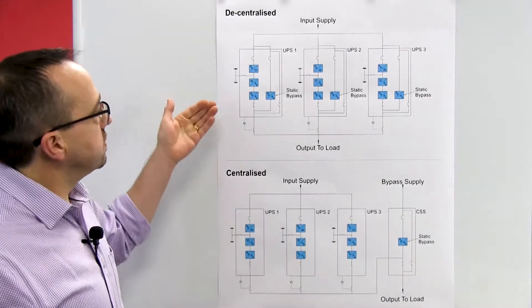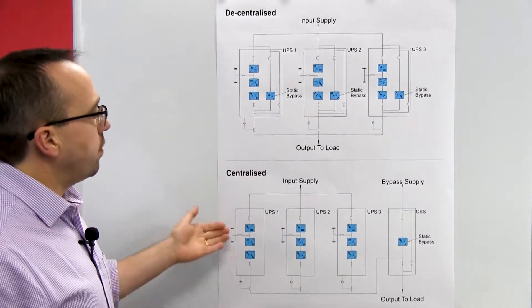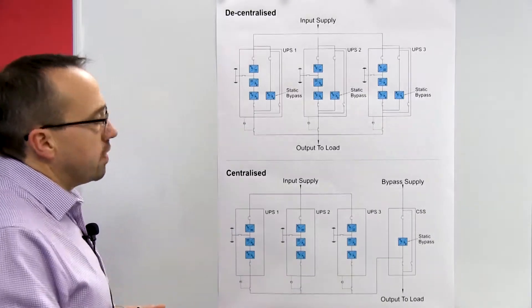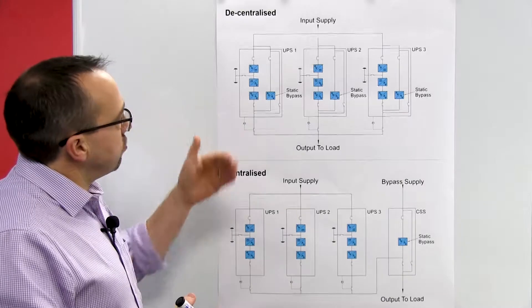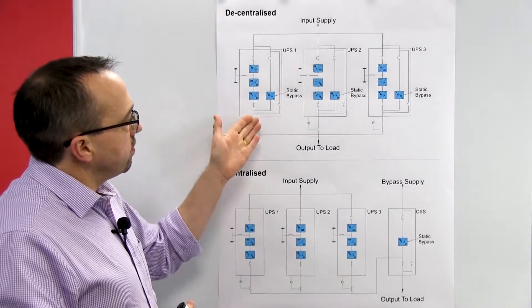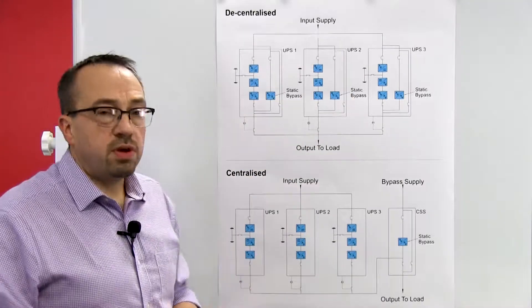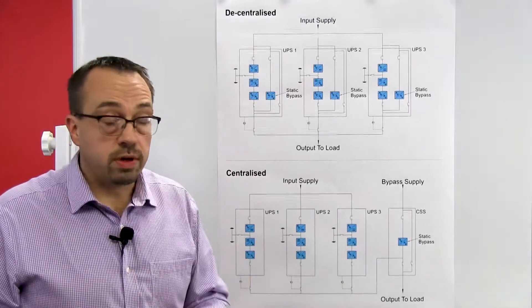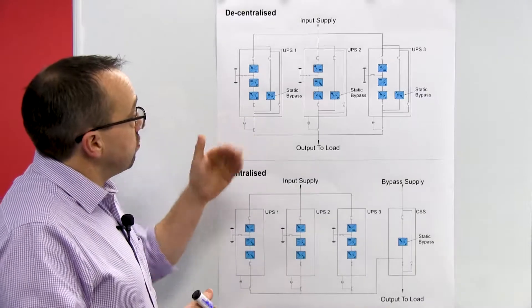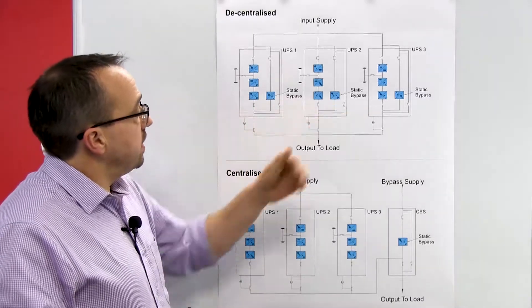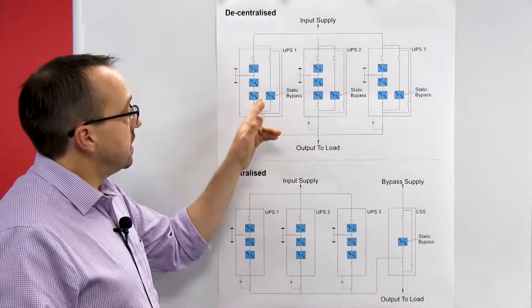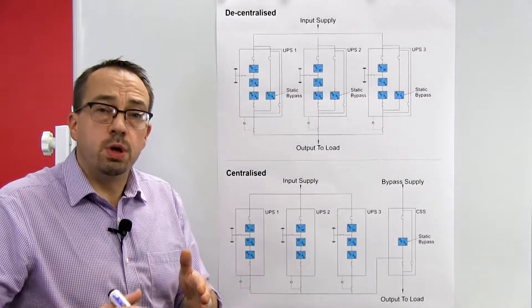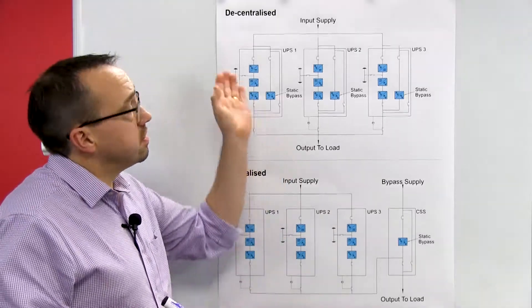On the board here we have two systems: the decentralized system and the centralized system. The main difference is the location of the static bypass. In the decentralized system we have three UPS systems — one, two and three — and you can use either more or less. Inside each UPS there is a dedicated static bypass per UPS, so the bypasses are split across the UPS modules and hence they are decentralized.